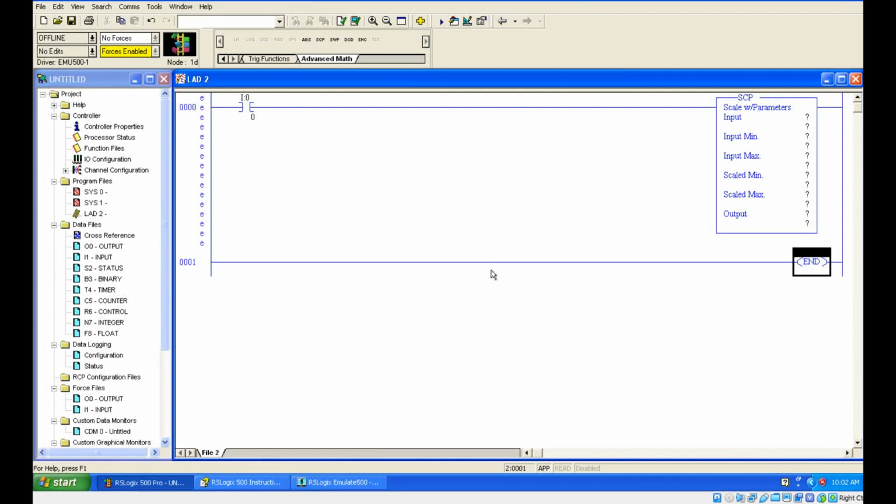So for this, in a ladder logic program, we need to compare, correct? We need to compare our tank value. When it is 20, we should be completely open. We need to send a signal for that as an analog output. Same, 50% open means we need to give 50% open when the tank value is 50. When the tank value is 75, like that, here we need to use the comparator functions. Correct? So for that comparator function in the ladder logic, we cannot give 4 to 20 milliamps directly. For that, you need to do the scaling function.